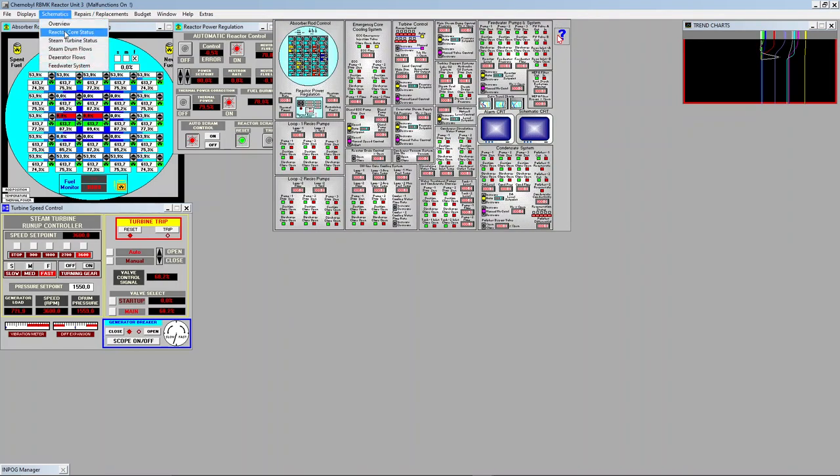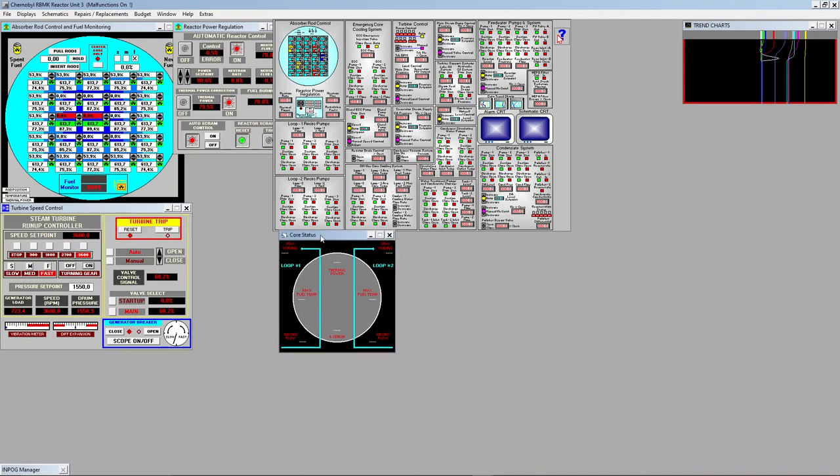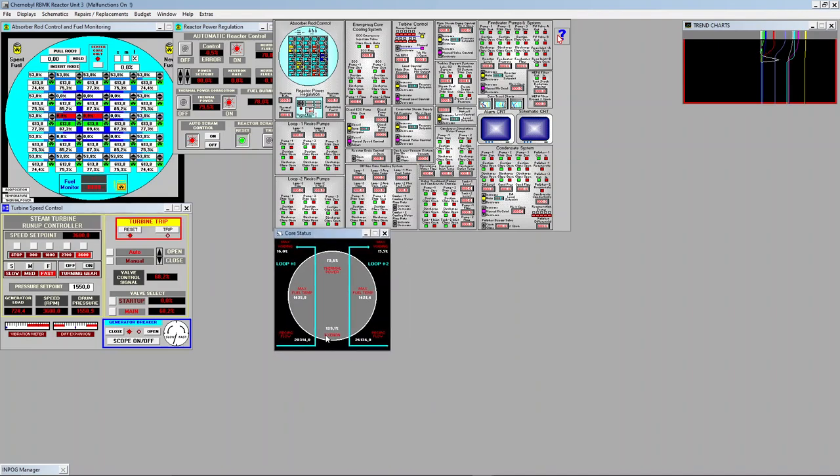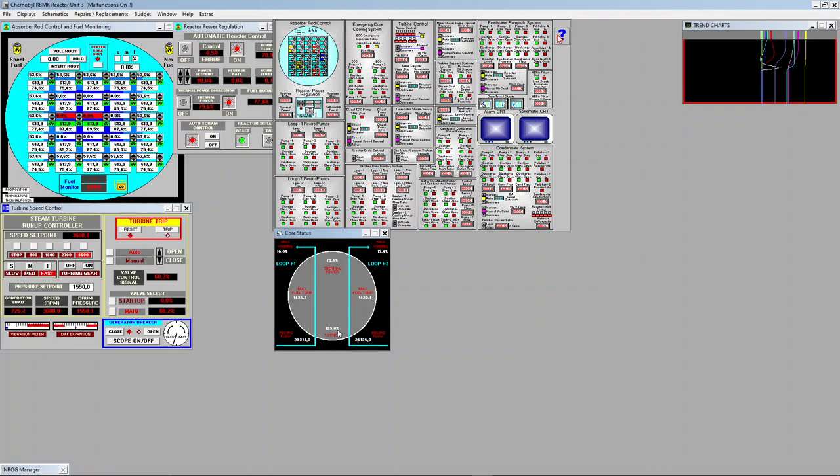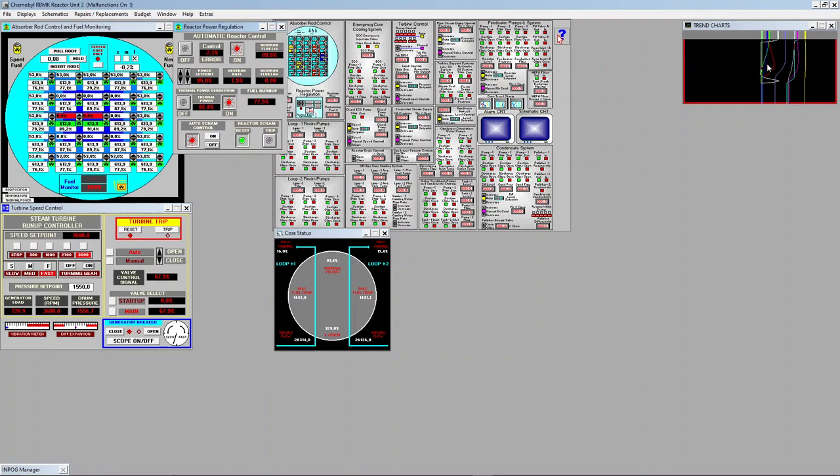Let's look at the reactor core status. Xenon is at 129.1. If the values are the same magnitude as in the demo version, that should be really far from poisoning. It's not surprising because a power of 80% is quite high actually. I will keep increasing power in the reactor to 85%. Trends look stable.